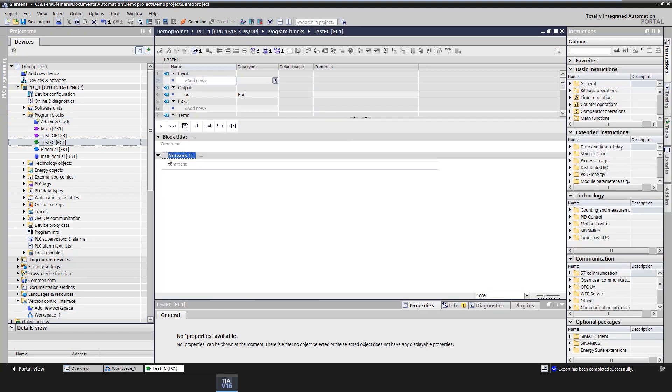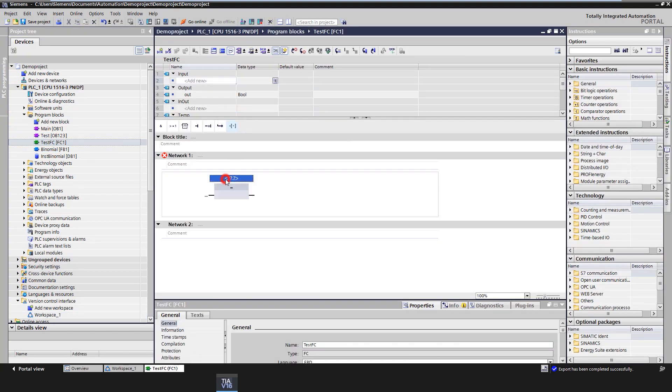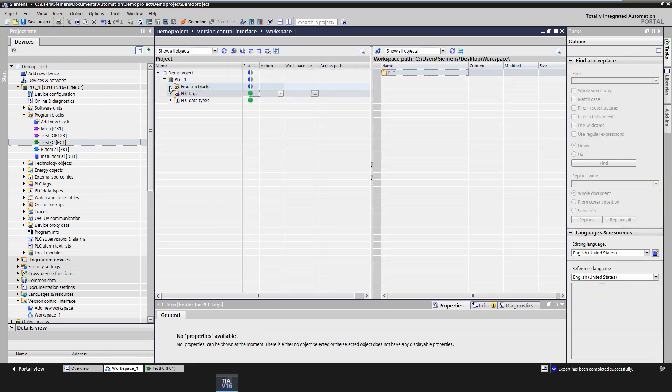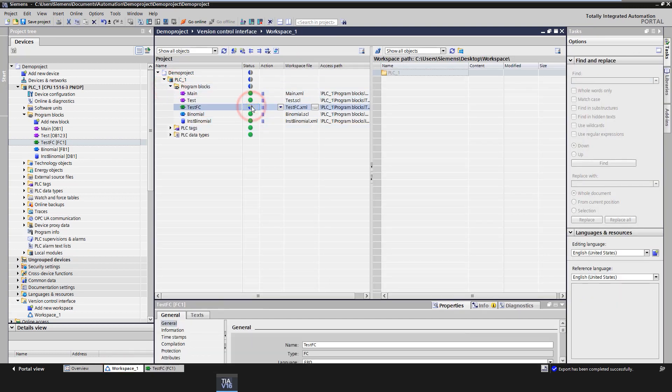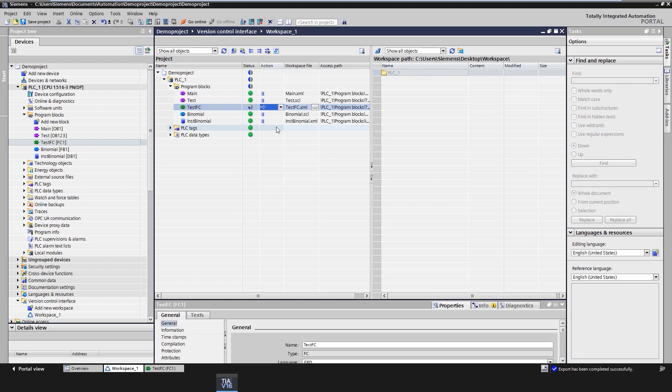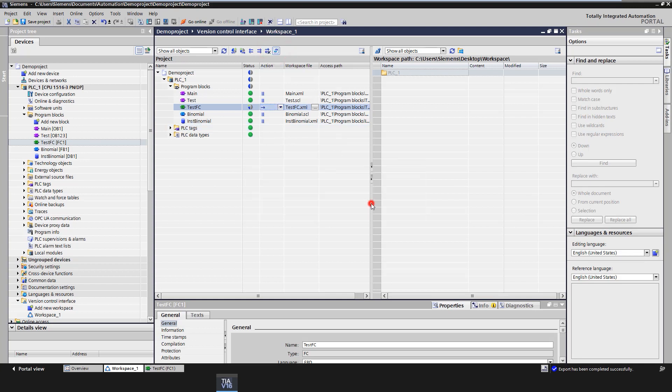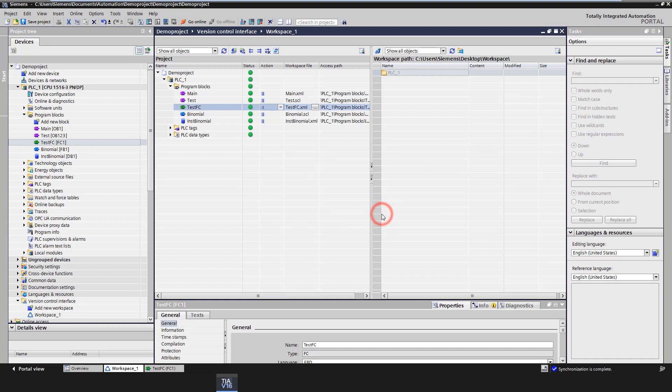If a synchronized element is now changed in TIA Portal project, this is indicated by a status indicator in the version control interface. Then you have the possibility to synchronize changed objects from the project to the workspace and vice versa. To do this, first select the direction of synchronization via the drop-down menu, and then synchronize the Portal project with the Windows workspace via the synchronize button. After successful synchronization, the status of the element is green again.